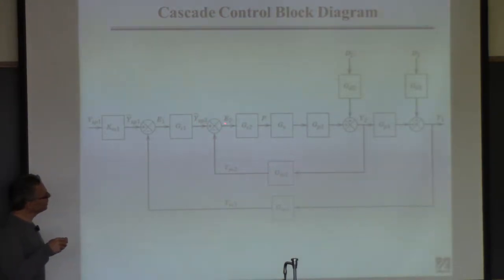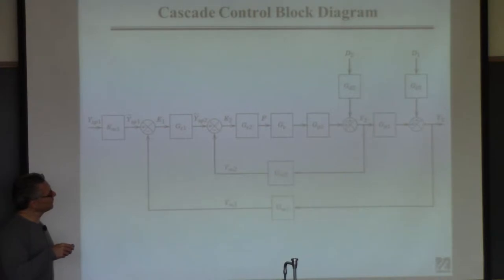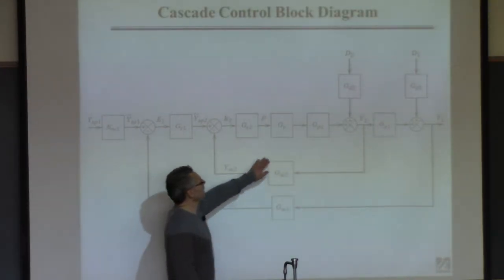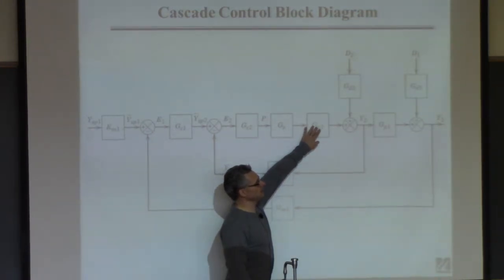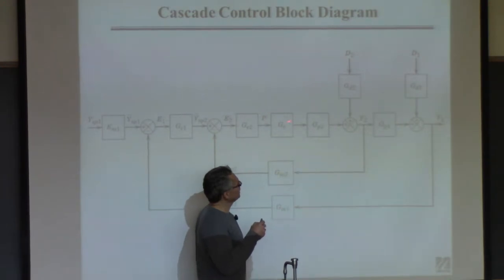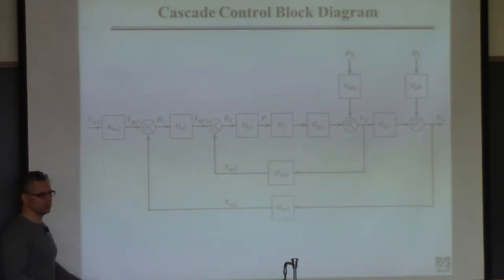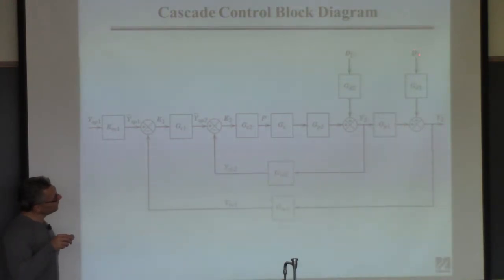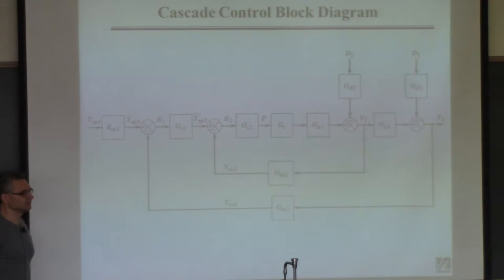In the inner loop, we measure this output — and the selection of this output is critical for the inner loop to be effective. We compare it to the set point provided by the outer loop, generate an error signal, it goes through the inner controller, generates a signal sent to the valve. There might be an inner process; for the examples I've given you the inner process is the valve. We might also have two types of disturbances: one that enters the outer loop and one that enters the inner loop.